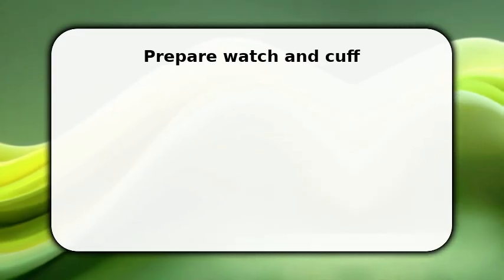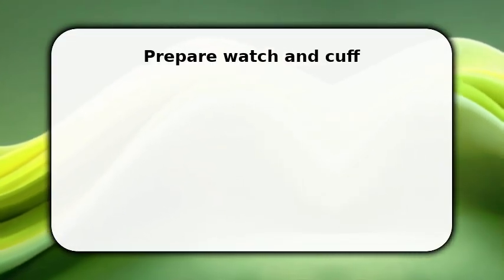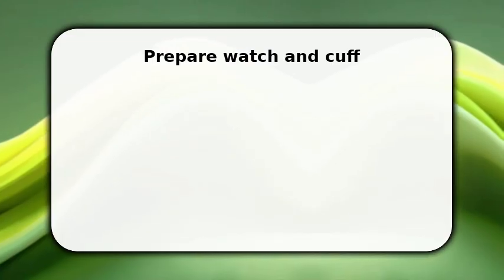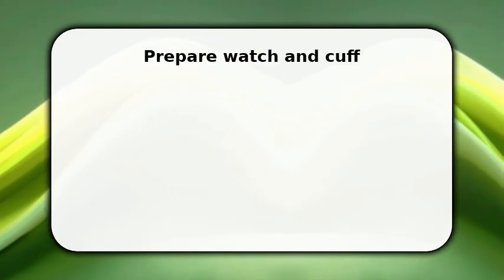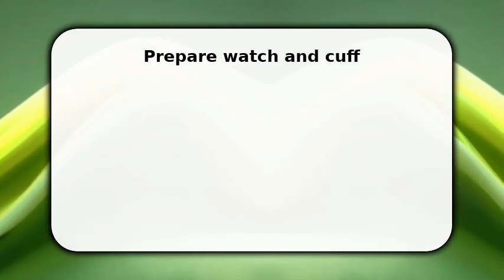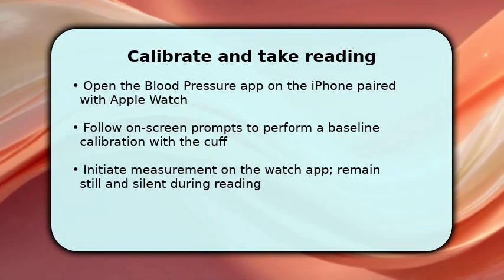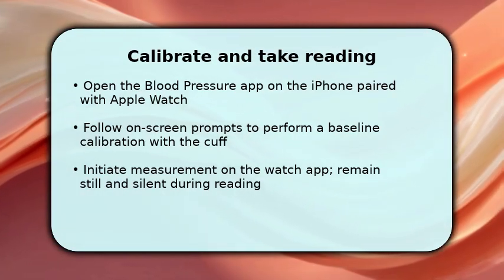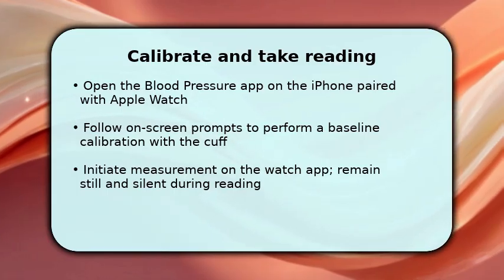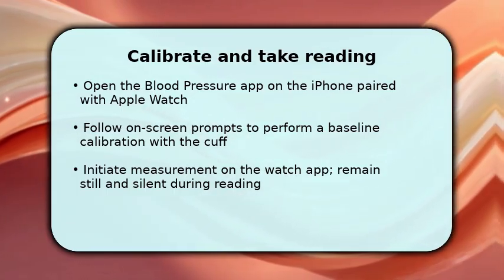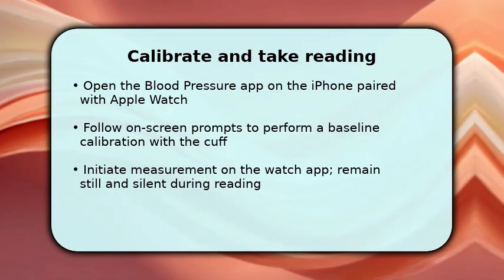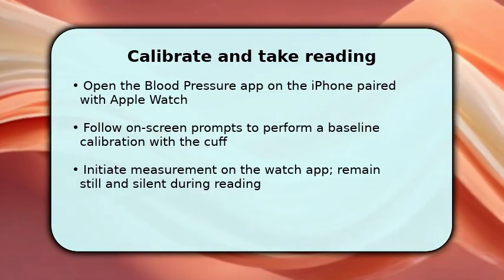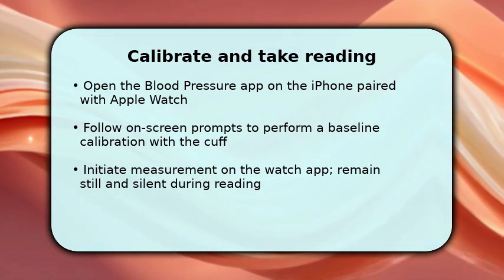Make sure Bluetooth and wrist detection are active on the watch and iPhone so data can sync automatically. This prevents lost measurements and prepares the system for the reading. You perform calibration next, which maps cuff values to the watch algorithm for accuracy. Open the blood pressure app on your iPhone, follow the guided steps to take a baseline reading using the external cuff, and allow the app to store that calibration.